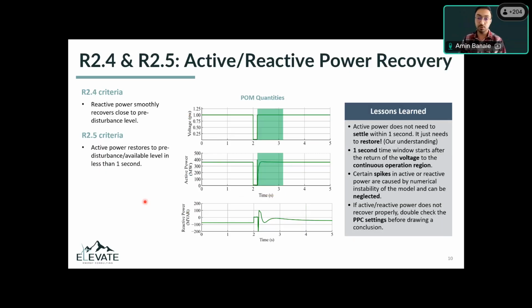And then R2.4 and R2.5 are about active reactive power recovery. A few points here as well: how we approach it is that we apply 100% voltage dip at the POM of the plant, and then we look at active and reactive powers and how fast they recover and how smoothly they recover. For R2.5, PRC-029 wants a 1 second time window for active power recovery. The way we understand this requirement is that this 1 second is for active power to restore, and it does not necessarily mean that it has to settle, and that's totally our understanding. And based on our experience, 1 second is not enough for active power to settle fully.